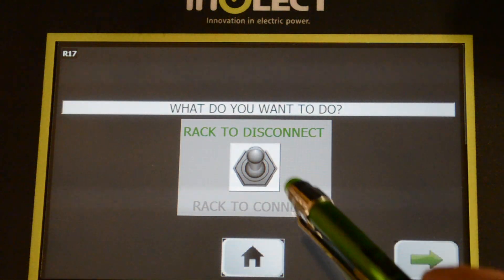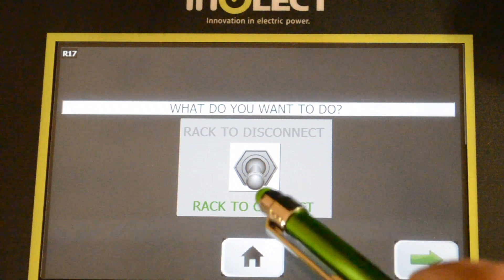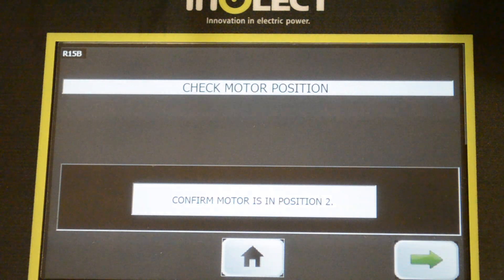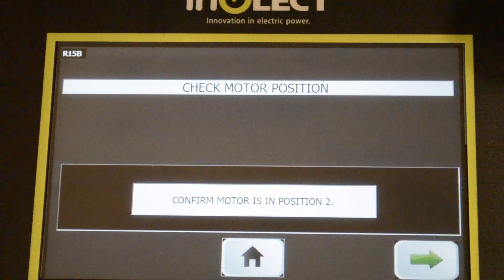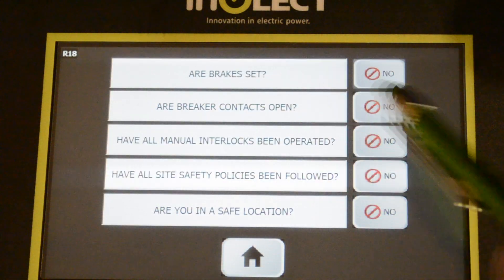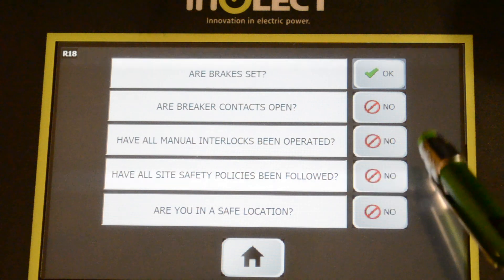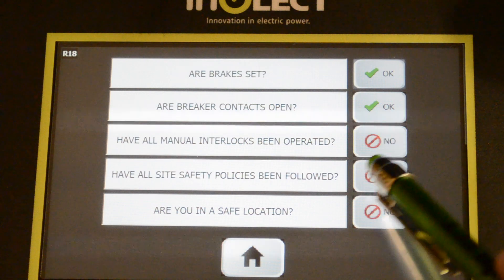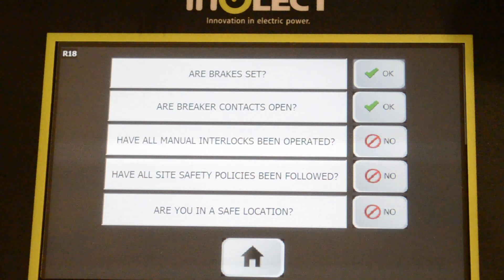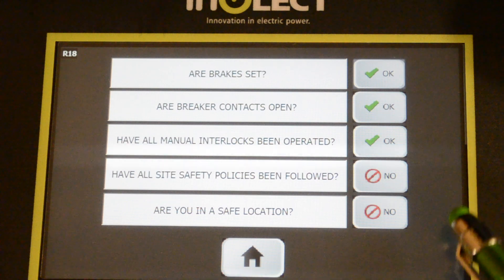What do you want to do? You either want to rack to disconnect or connect. Our breaker right now is in the disconnect or rack-down position for the Magne-Blast, so we're going to rack it up to connect. Check the motor position — confirm the motor's in position two. We've done that by moving the motor's horizontal stripe into the numbered position on the motor carriage. Then there's a safety checklist: Are the brakes set? That's our hand brakes on the wheels. Are the breaker contacts open? We don't want to rack a closed breaker — that's a major safety concern. Have all manual interlocks been operated? This could be Kirk keys or an actuated style interlock. You want to make sure that racking screw is free-moving before pressing go.